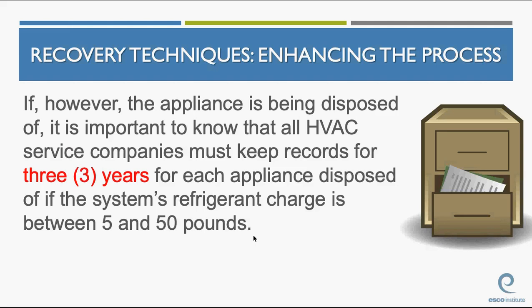If the appliance is being disposed of, okay, you have to keep records for 3 years for each appliance being disposed of if the system's refrigerant charge is between 5 and 50 pounds. So in other words, if your service company pulls out a system and disposes of an R22 system when they put in an R410A system, they're required to keep the records for 3 years for each appliance being disposed of: basically how much refrigerant was recovered from it, what was done with the refrigerant, and what was done with the appliance.